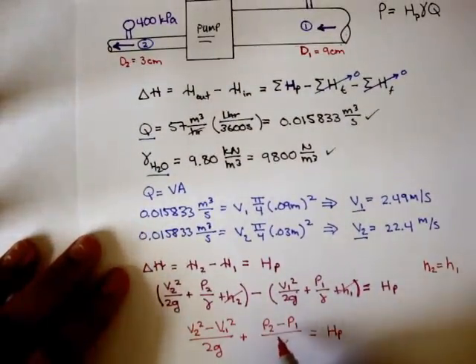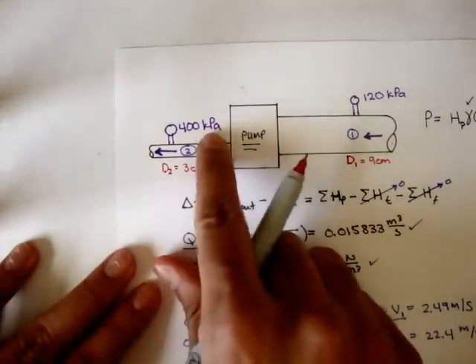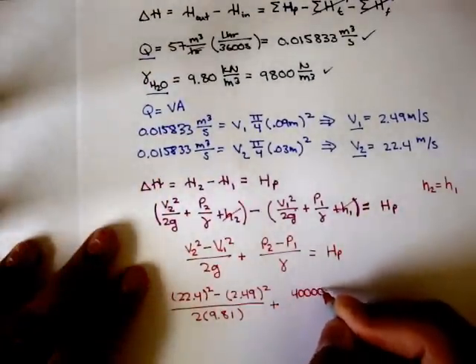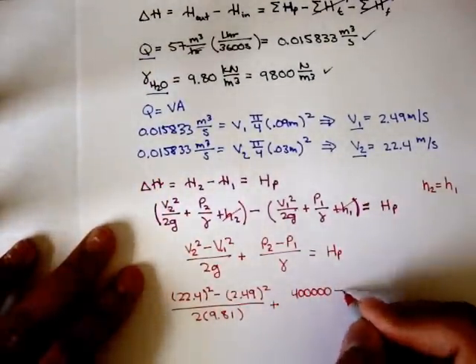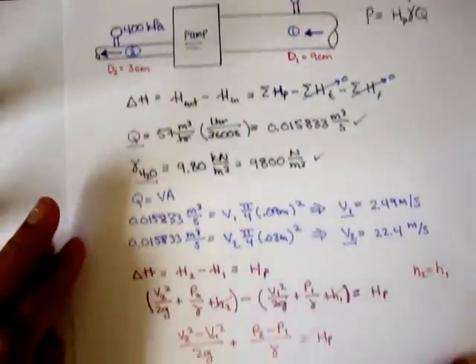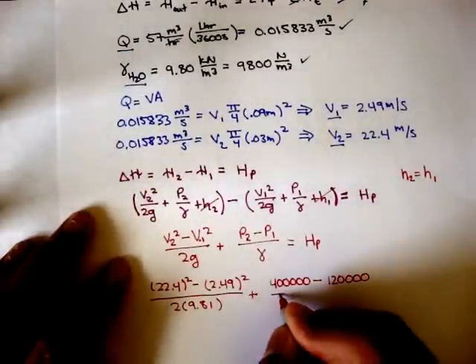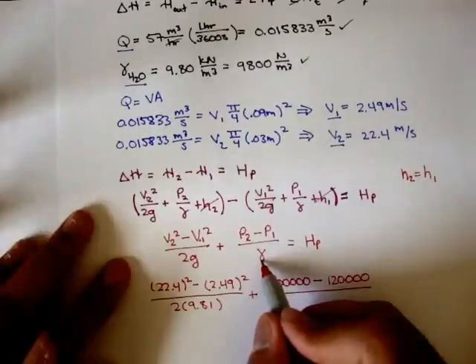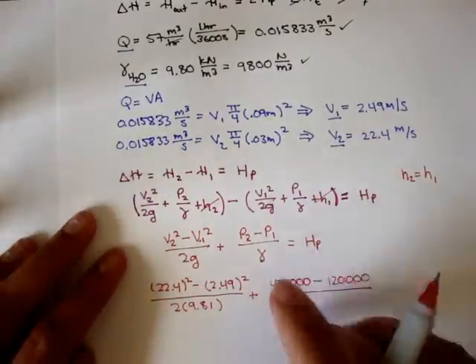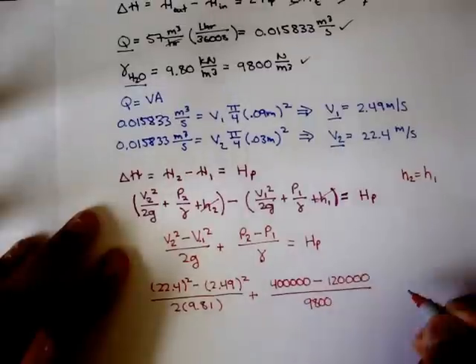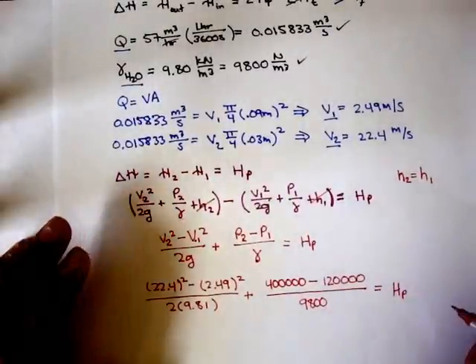So the pressure at 2 is 400,000 minus the pressure at 1 which is 120,000 pascals, over the specific weight of water which we found to be 9,800 newtons per meter cubed. And all of this is equal to the pump head.